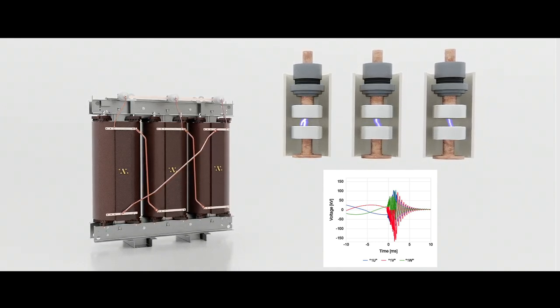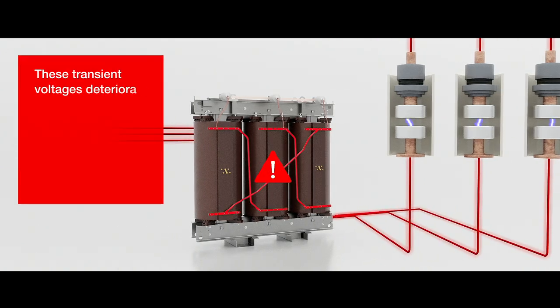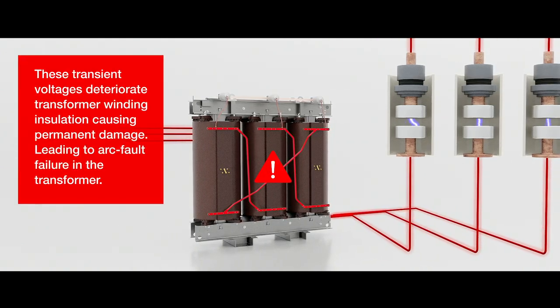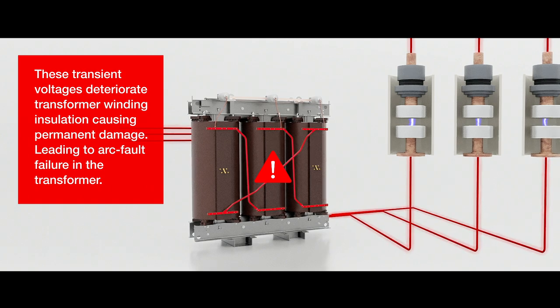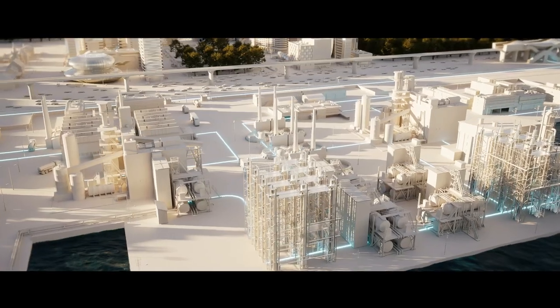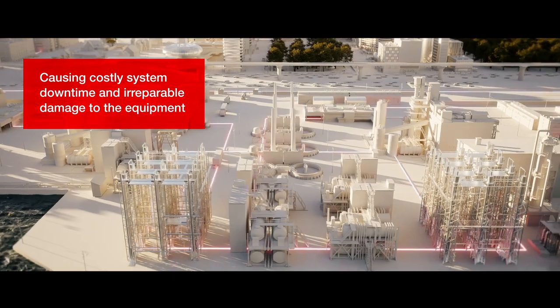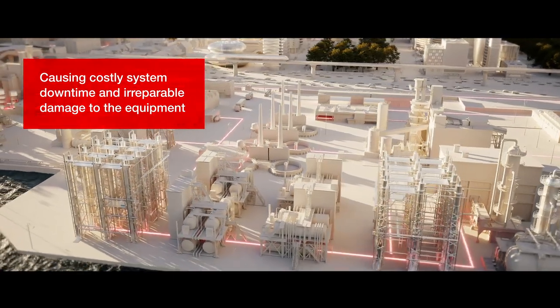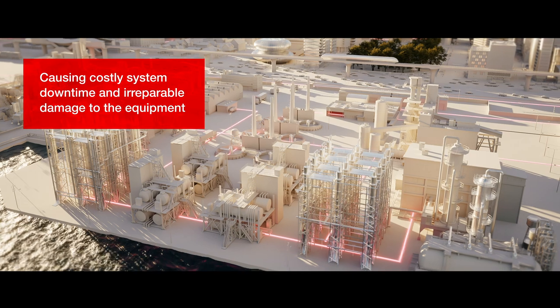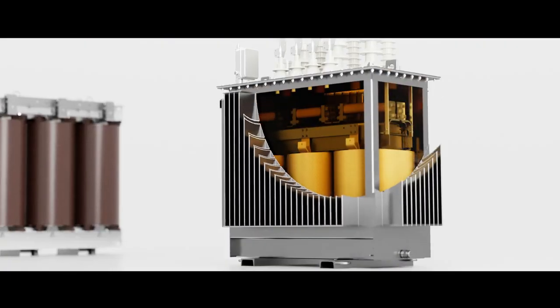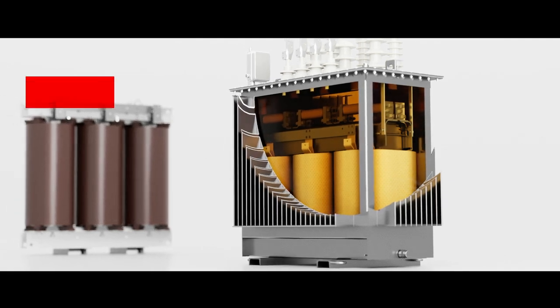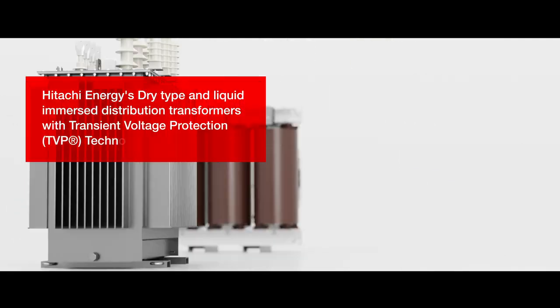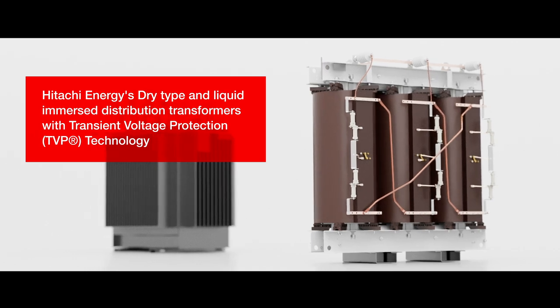These transient voltages slowly deteriorate the winding insulation, causing permanent damage, which over time may lead to an arcing fault failure in the transformer. These failures, though rare, cause unplanned system downtime and irreparable damage to the equipment, both incredibly costly to network managers.